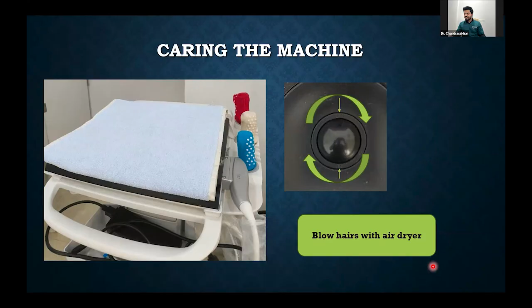Often, maybe once in 15 to 20 days, you may have to open this thing, which is a trackball, where you can find a lot of small, minute hair trapped. So you have to keep on checking this one. And once your scanning is done, always blow dry your ultrasound with the help of a hair dryer. These are the practical things which you have to do to take care of your USG machine. Then your USG machine will take care of you.